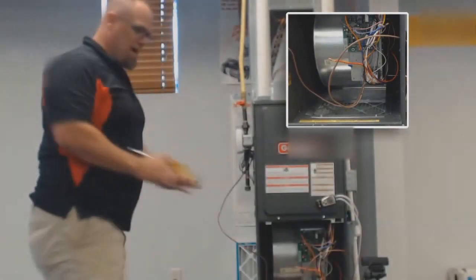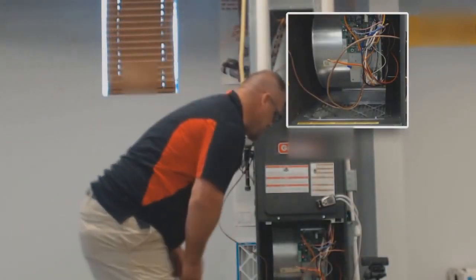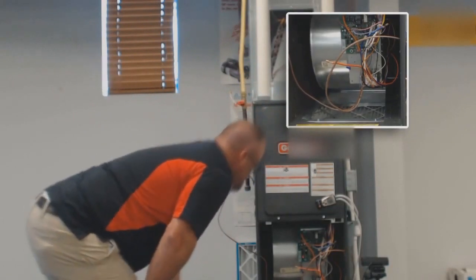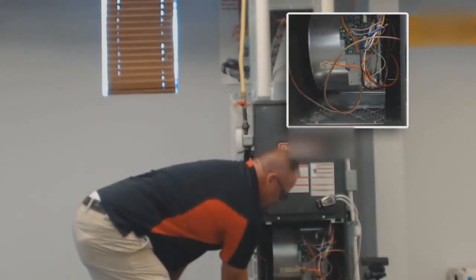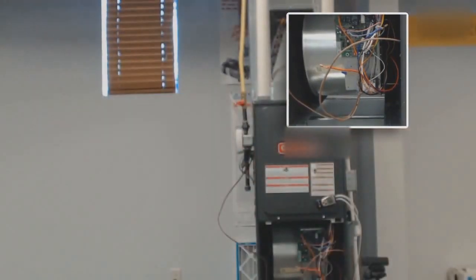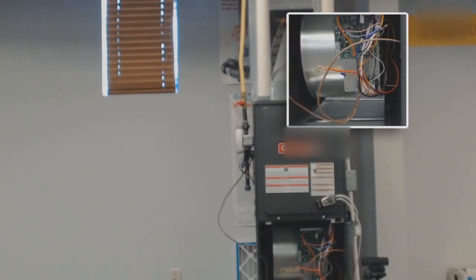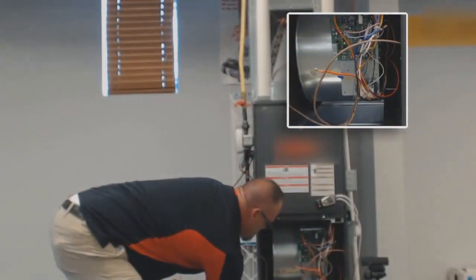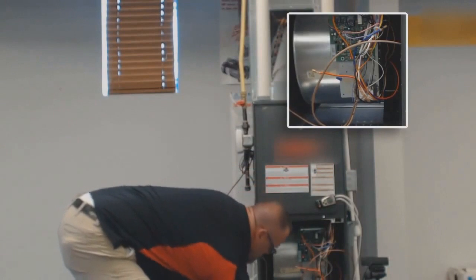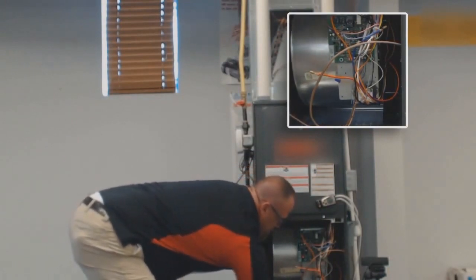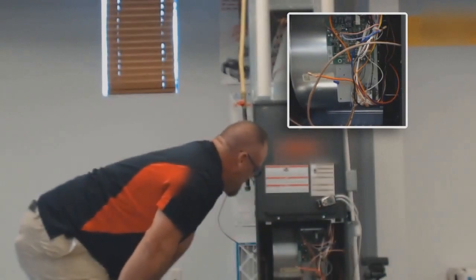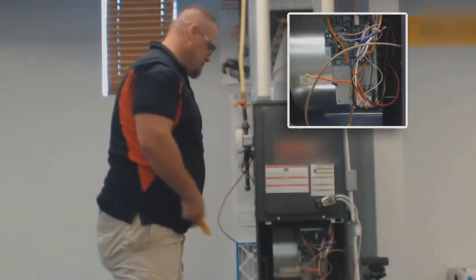But right now, I've already set this up. So I know that we're set up for the proper blower speed right now as it sits. As you'll notice, we've got the orange wire in here. The orange wire is actually the wire that we're using, and it's low speed, and that's because I've already measured this. I have my manometer already hooked up. I'm going to go ahead and put in a regular old filter. Okay, and these fiberglass filters are the ones that we're supposed to be using in a furnace. Even though most people use the Merv 11s or something like that, the manufacturer uses the fiberglass filters.